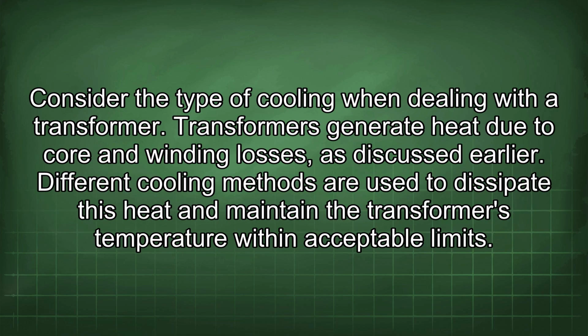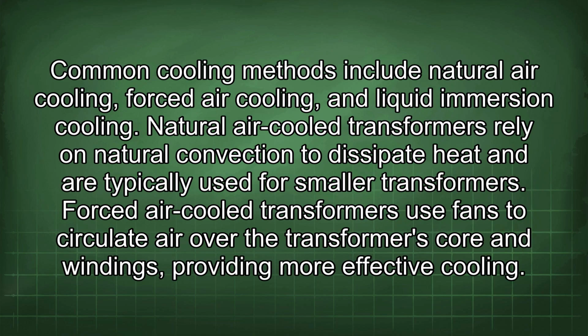Consider the type of cooling when dealing with a transformer. Transformers generate heat due to core and winding losses, as discussed earlier. Different cooling methods are used to dissipate this heat and maintain the transformer's temperature within acceptable limits. Common cooling methods include natural air cooling, forced air cooling, and liquid immersion cooling.